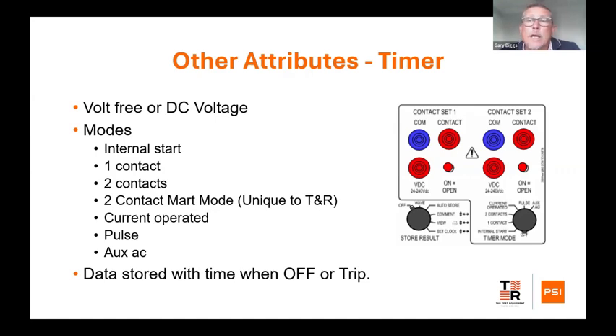What happens is you press the output button. When you press the output on, the timer will automatically start, and when the relay trips, the timer will stop. When the relay trips, it will not only stop the timer, it will actually turn the output off, so that you're no longer feeding a relay with an input.